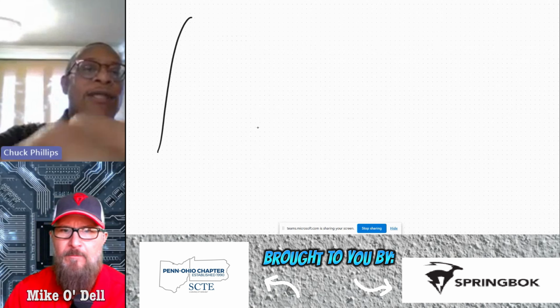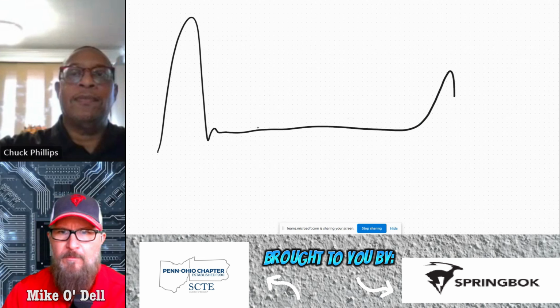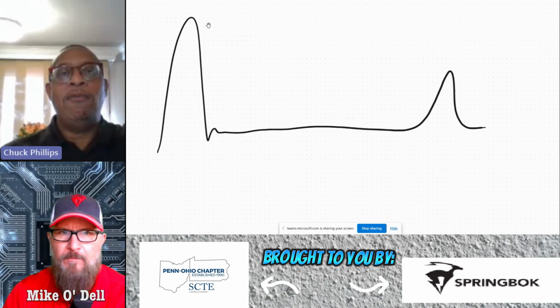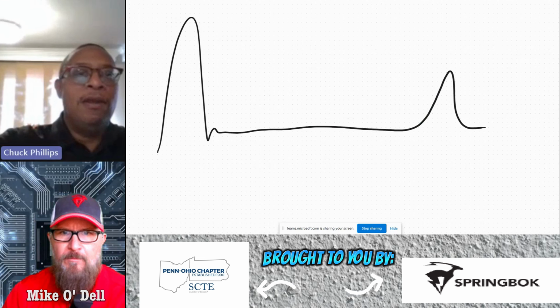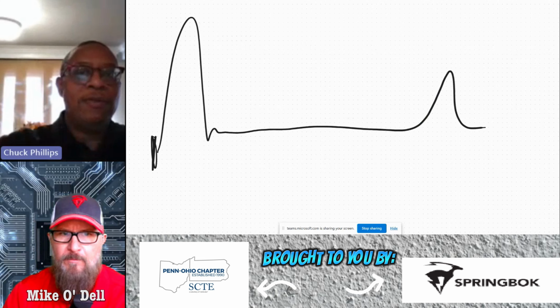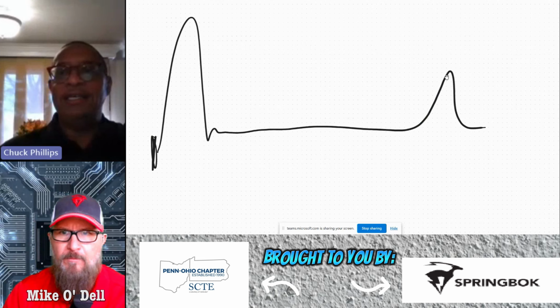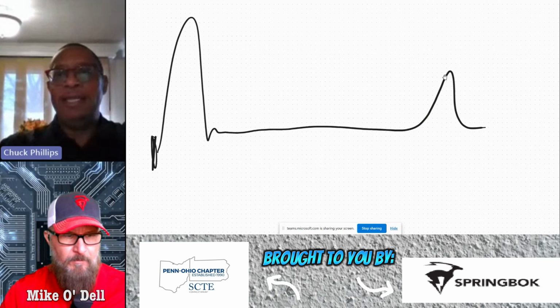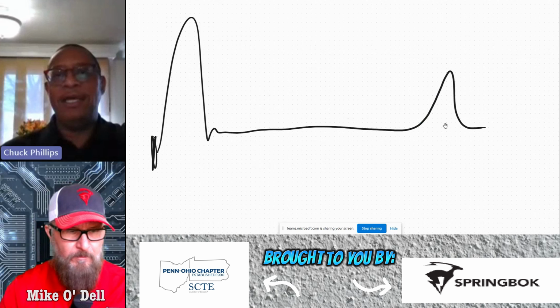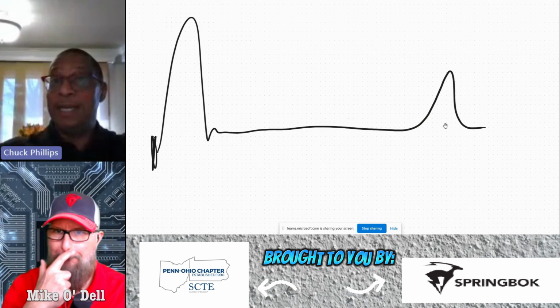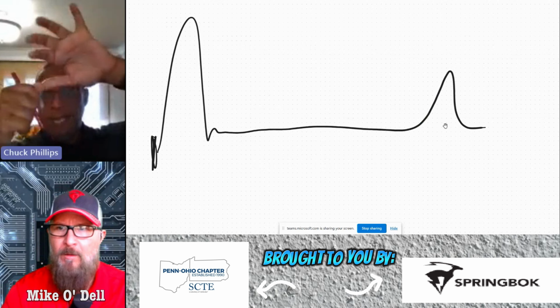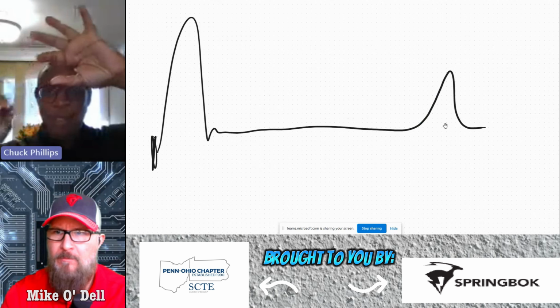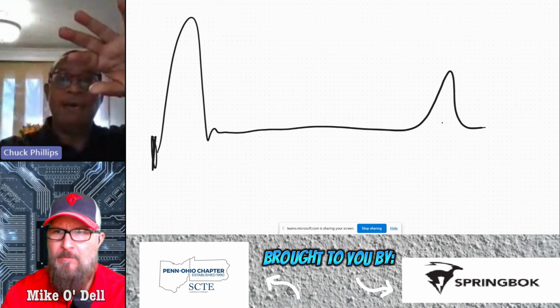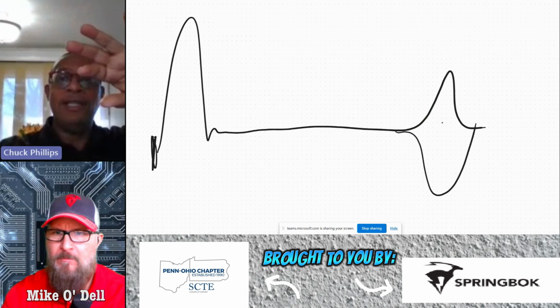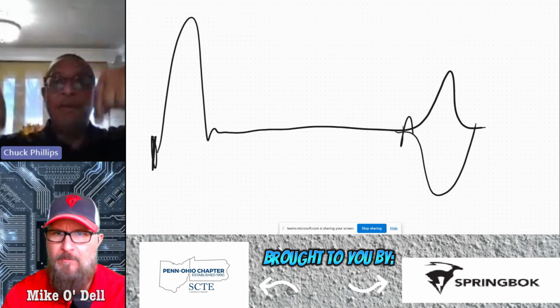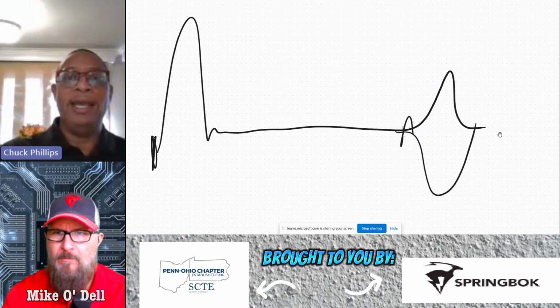So if I have a waveform that looks something like this, this represents the output pulse where the signal starts. Right here is 0 where the signal starts. And then this would represent an open at the end of the cable. It's disconnected. There's nothing there. It's just a complete open cable. If I were to take that cable and short it out, either the center conductor versus the outer, you're going to see that flip from an open to a short, and that's what you're looking at.